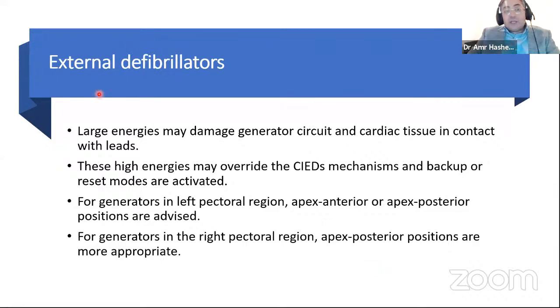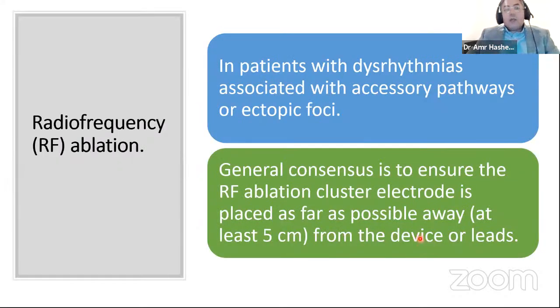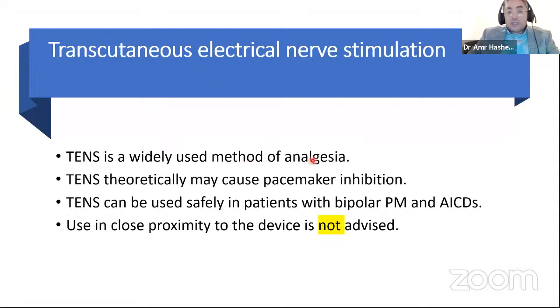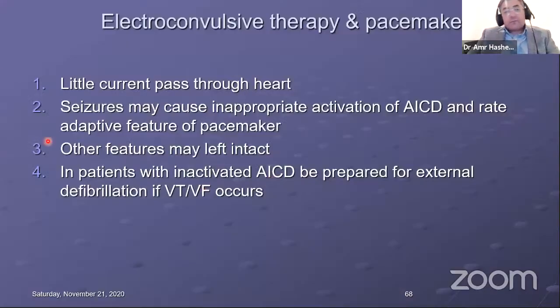To reduce diathermy risk: use bipolar diathermy or ultrasonic harmonic scalpel; if unipolar is necessary, position so current does not pass near the device or leads; use infrequent short bursts at the lowest feasible energy; have temporary pacing and defibrillation available. For external defibrillators, place pads in apex-anterior or apex-posterior positions away from the generator. For RF ablation, the cluster electrode should be at least 5 cm from the device or leads. TENS may theoretically cause pacemaker inhibition but can be used safely in bipolar pacemakers and AICDs if kept away from the device.